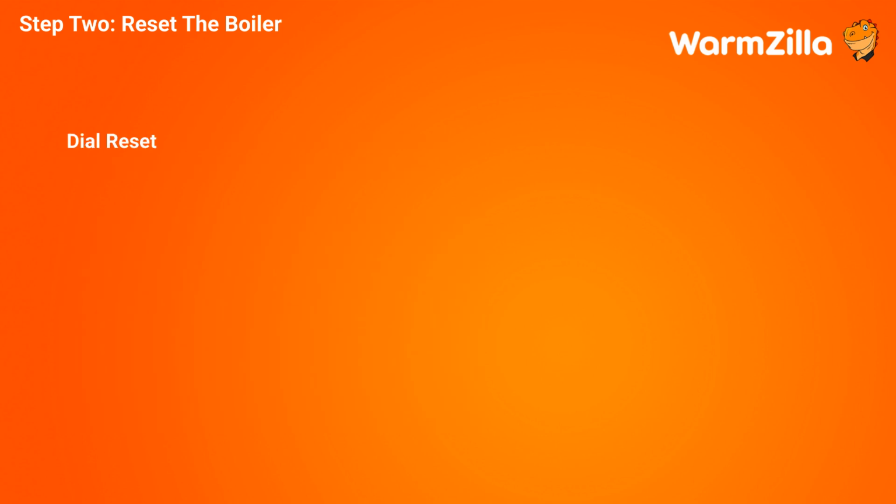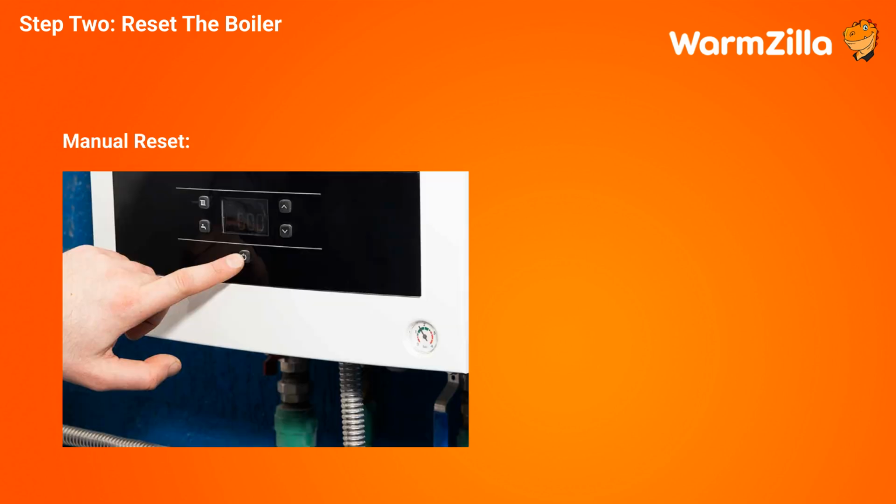Dial reset. Generally found on older Combi boiler models or entry-level units, a dial reset is usually integrated into the main selector. To reset these Combi boilers, you will likely need to turn a selector dial to the reset position for a few seconds, which will clear the error message and return the unit to its usual heating mode. Manual reset. Older models may have a small manual button on the boiler's panel that must be pressed firmly. If everything has gone perfectly, reigniting the boiler will take a minute or two.